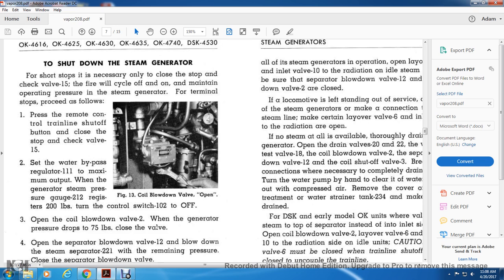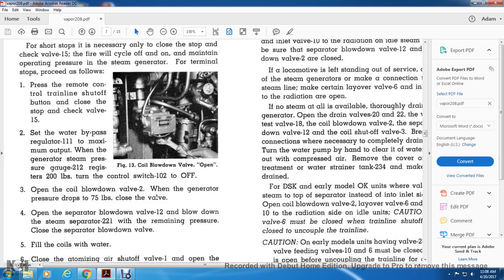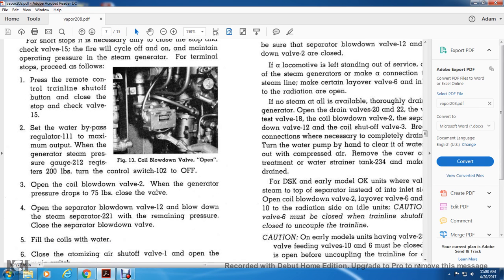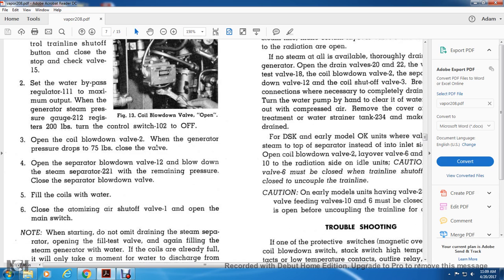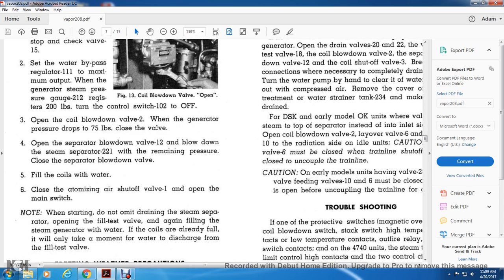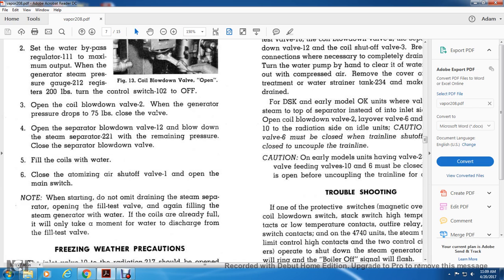Open the coil blowdown valve 2 until the water regulator pressure drops to 75 pounds. Close the valve. 4. Open the separator blowdown valve and blow down steam separator 221 with the remaining pressure, then close the separator blowdown valve. Fill the coils with water. Close the atomizing air shutoff valve. Open the main switch. Note: when starting, do not omit draining the steam separator by opening the fill test valve. This will also fill the steam generator with water. If the coils are already full, it will only take a moment for the water to discharge from the fill test valve.